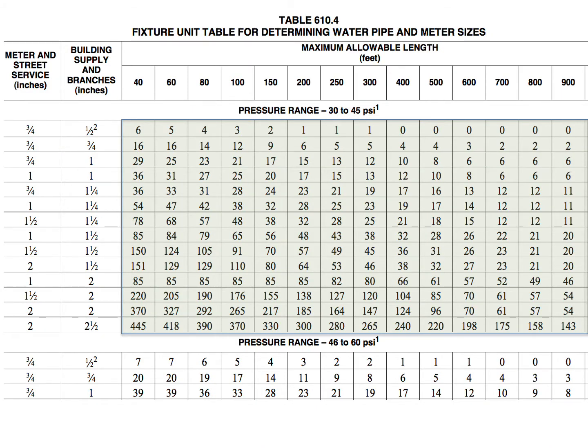Table 610.4 is the table we use if we are going to do the simplified method for sizing a water distribution system. If we look at the table, we see a highlighted area underneath pressure range 30 to 45 psi, and all the numbers in that shaded area are simply fixture units at any given point in the building — it could be on a branch, on a riser, your building supply, or even your street service coming in. They are fixture unit totals, and part of this video is talking about giving flushometer valves a fixture unit value.